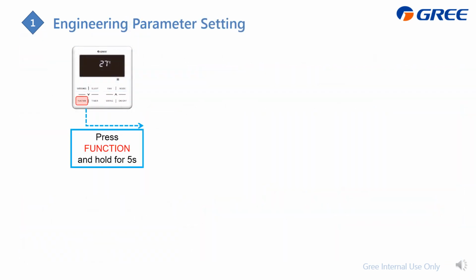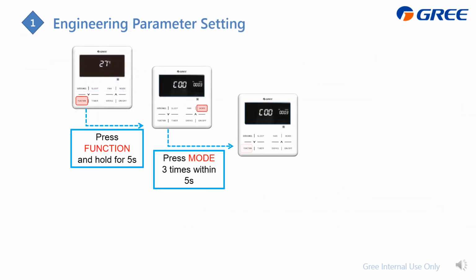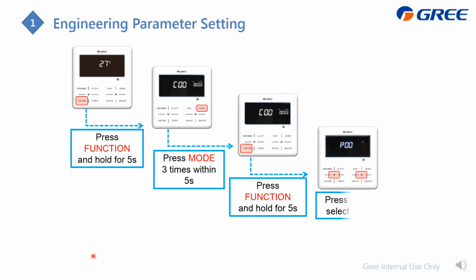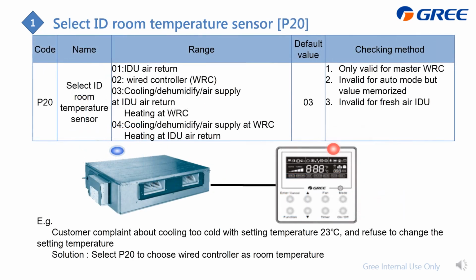This is the engineering parameter setting password. For this one, you are going to change the corresponding codes for different parameters and functions. This will affect the system performance and also the operation. I will introduce the most commonly used items just for your reference. The first is the indoor unit room temperature selection. The code is P20.